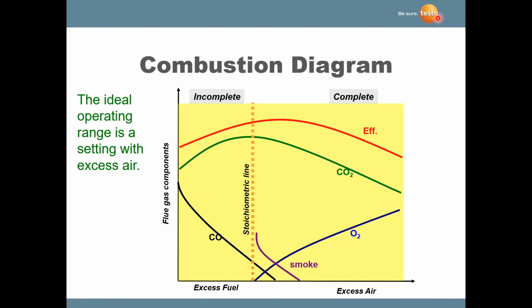If you didn't get that part of it, here's a diagram again. The diagram I showed you previously was mainly natural gas, but in this one I've added a smoke line. What Beckett here in the United States is saying is check the smoke first. Make sure you have a trace of smoke, which means you're not way up here at an 8 or 9. You're down here at a 2 or 1. Once you get that 1, let's say, you use a combustion analyzer and you measure at that point, and you may get 4.5% oxygen. Beckett is saying, now increase that oxygen from 4.5 to 5.5. If we do that, we're away from the smoke line. We've got a 5.5% oxygen. We're high in the CO2, and we still maintain good combustion efficiency, which means we have a safe operating appliance.